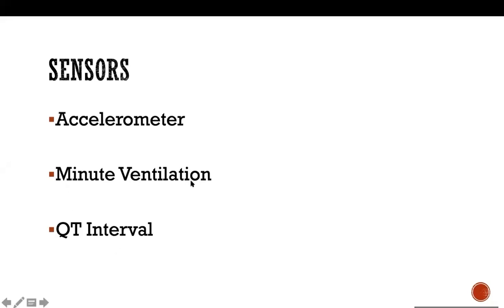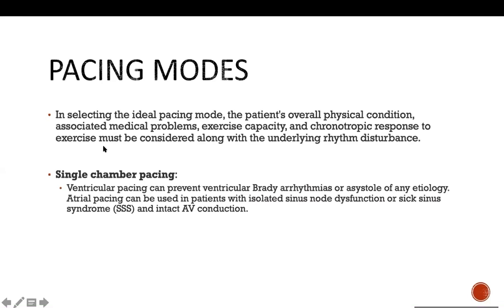The second thing is minute ventilation. The lead itself might be able to sense the change in intrathoracic impedance that results from an increased respiratory rate, which results from increased activity. If someone is going up and down the stairs, their breathing is heavier, they're a little bit more tachypneic. With the sensor, the device is able to assess the minute ventilation, and an increase in that indicates increased activity. The same thing also, the lead might be able to measure the QT interval. Usually with increased activity there is shortening of the QT interval, and then the device would know to increase the heart rate. But the majority of the sensors in devices are accelerometers.